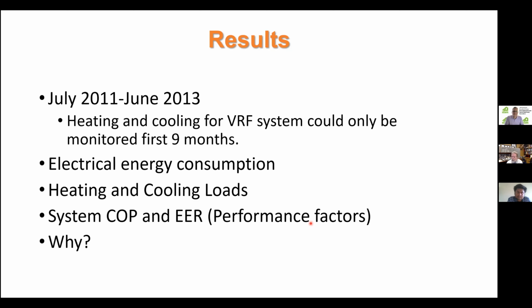So the electrical energy consumption for both systems was measured. The heating and cooling loads were measured as well. We had inlet and outlet temperatures, and flow rates from the flow hood measurements that were tied to each stage of operation. So we could reconstruct how much flow there was, and that allowed us to get the heating and cooling loads. And then we also computed what I now call performance factors, but we called the system coefficient of performance and energy efficiency ratio.